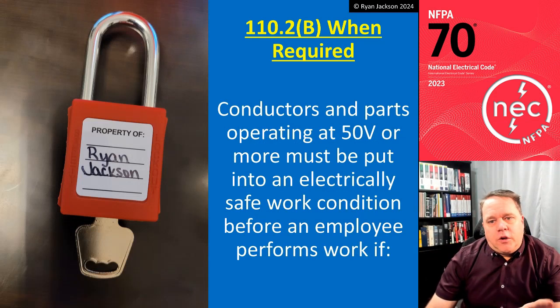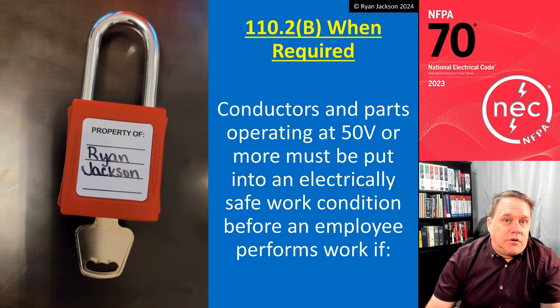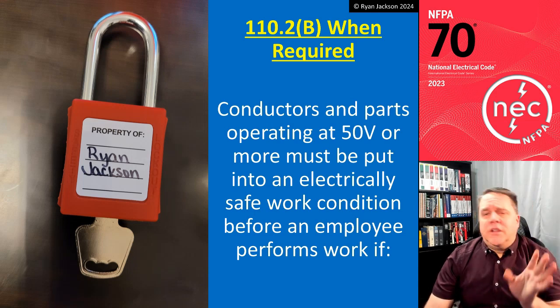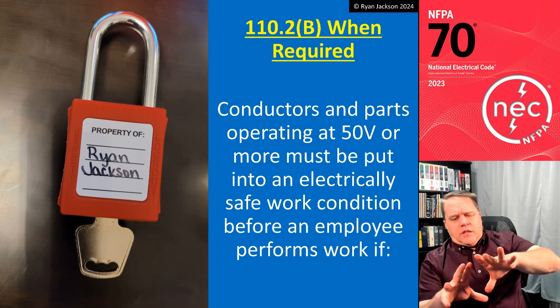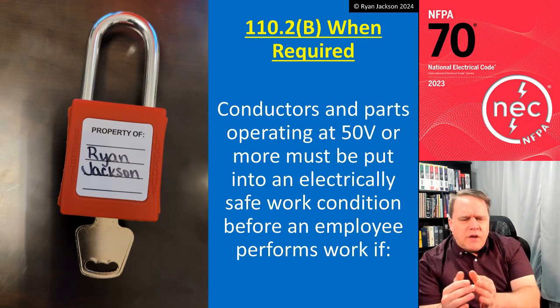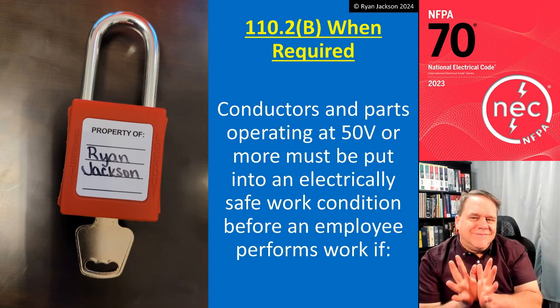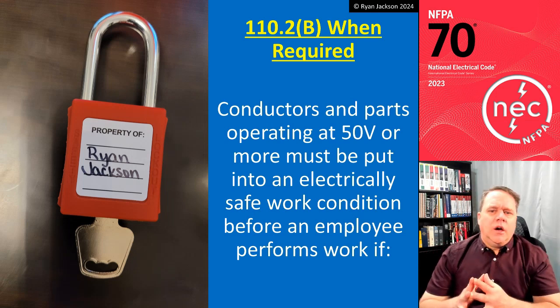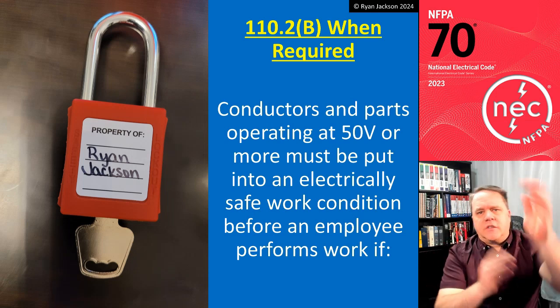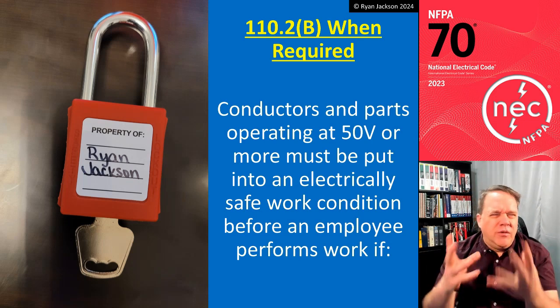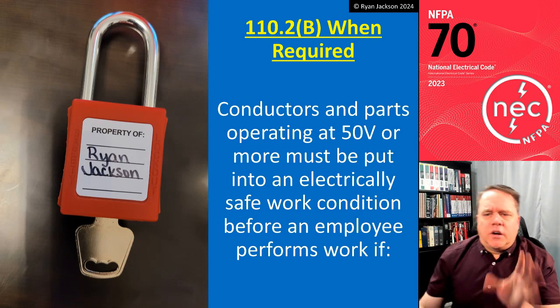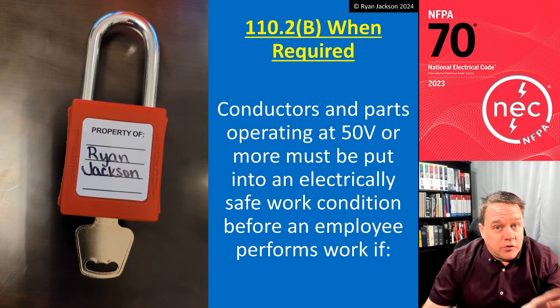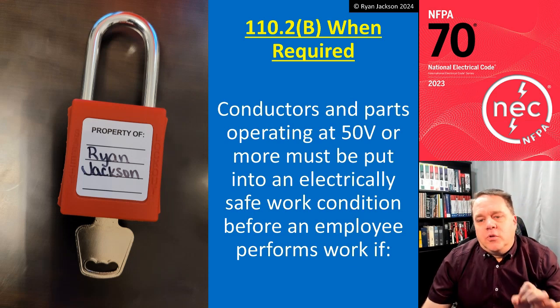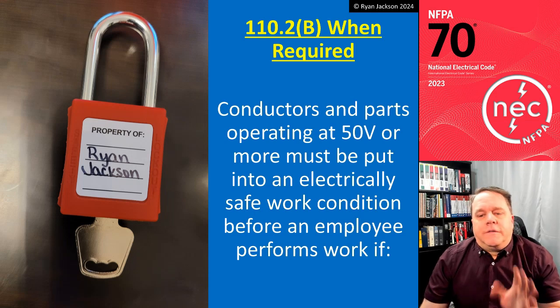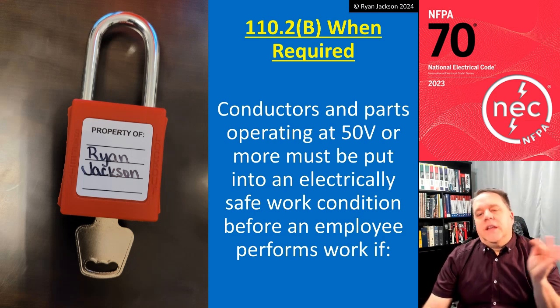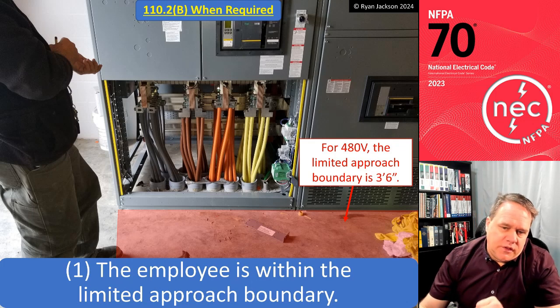110.2b. When required. When do you have to have an electrically safe work condition? Really, really important section here. They rewrote this section, kind of reorganized it from a technical perspective. Not much really changed here. What we used to have as positive text, we now kind of created into an exception, and they rewrote it, added some information. So conductors and parts operating at 50 volts or more must be put into an electrically safe work condition before an employee performs work if the employee is within the limited approach boundary.